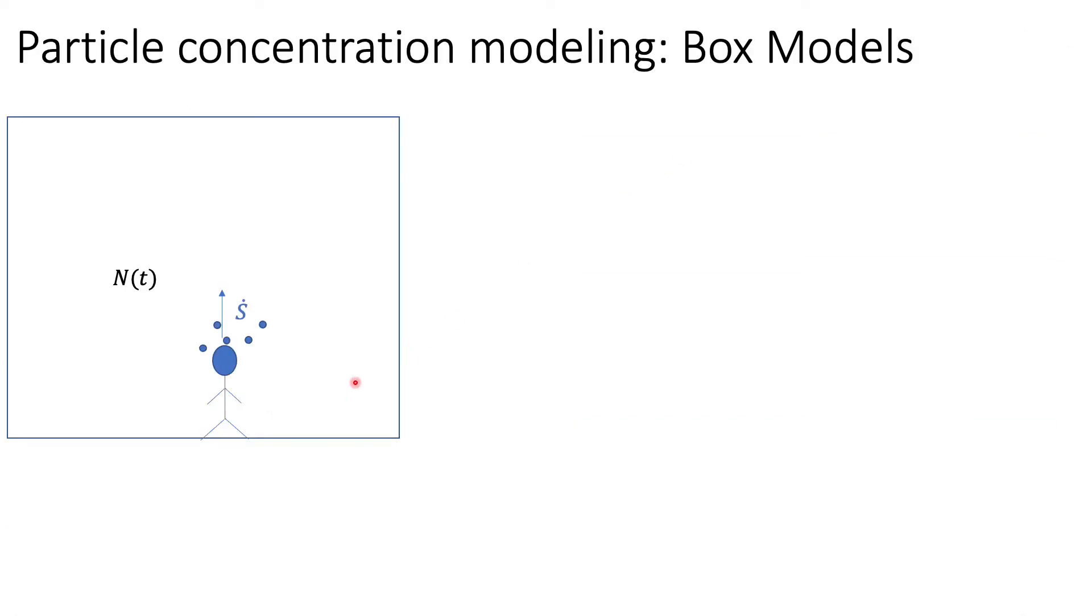My interest here is to understand what the fate of aerosol would be in a room. I'm going to consider this room as a box, so we'll call these box models. I'll have to consider the injection rate of the particles from a source, could be a person. We'll also consider the injection of flow through the ventilation system and the removal back to the ventilation system. In addition, these particles could be lost to the walls due to diffusion or gravitational deposition or could be resuspended back as a person walks around.